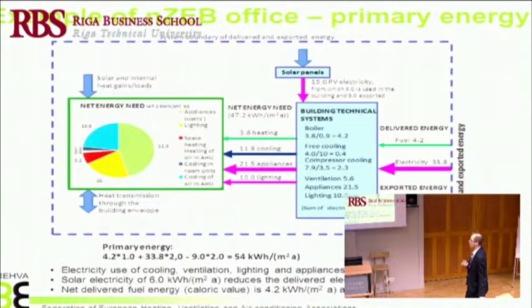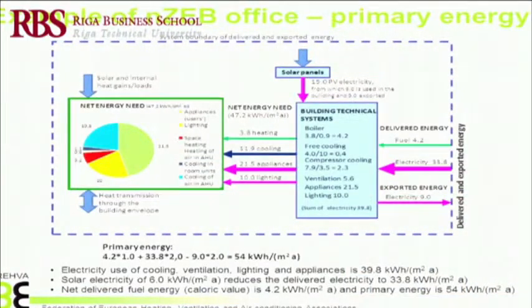Now you can take national primary energy factors and calculate the primary energy. It's given here: the primary energy factor for gas is equal to 1, typical for fossil fuel, and for electricity it's considered 2. So that's natural gas, this is delivered electricity minus exported electricity, and the same primary energy factors are used for delivered and exported electricity in this example, and the end result is 54 kilowatt hours.